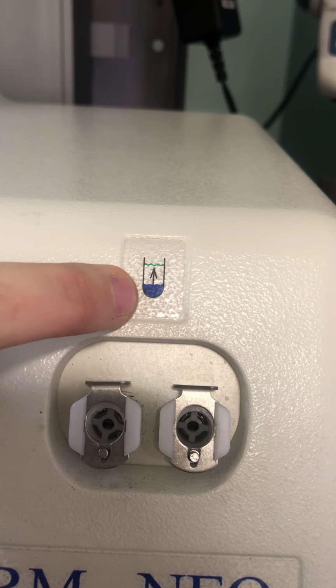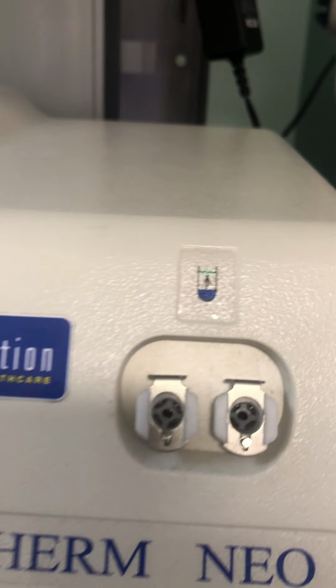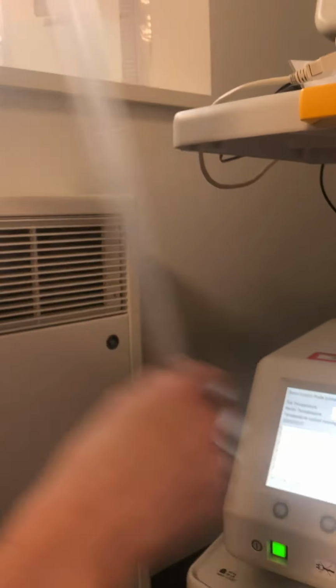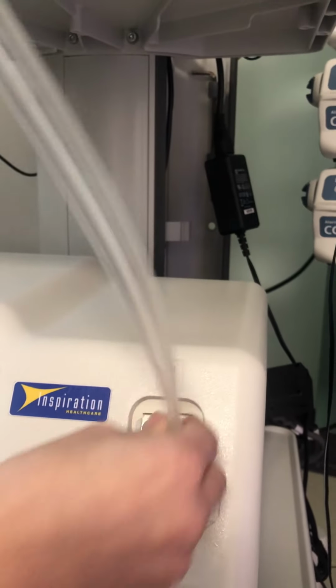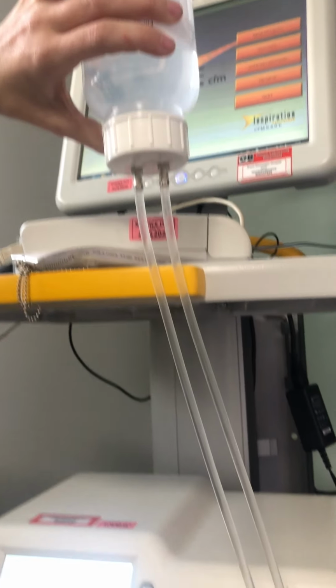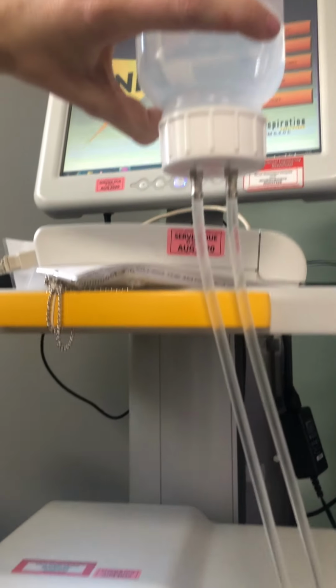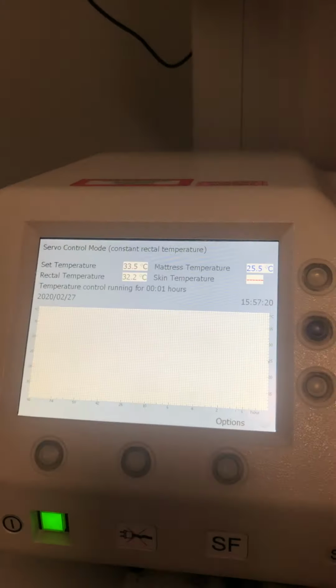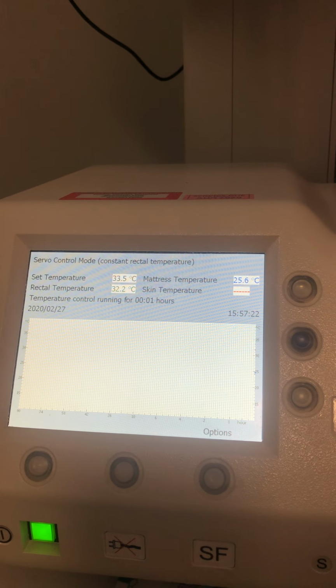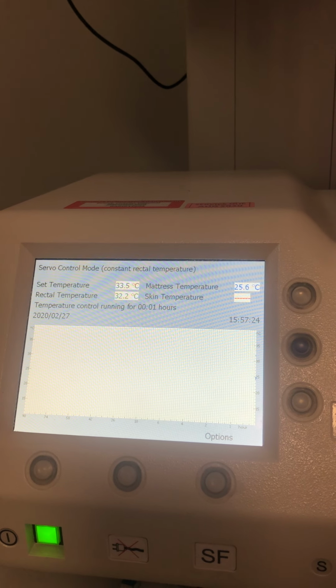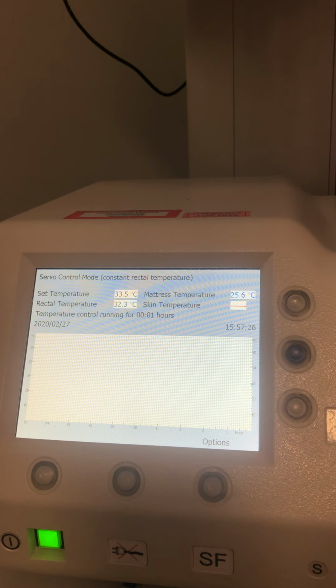What that's basically telling you is the mattress isn't full enough. So you don't need to go out and you don't need to stop it. All you need to do is reconnect your bottle like you had before. Reconnect the bottle and the mattress will automatically continue to cool the baby, but it'll also top up any deficit of water that's been lost when the machine's been put on. Like I said, as long as you top up the mattress beforehand, you shouldn't have a problem with this. It should always fill. This tends to be if you've got a long-term cooler, which we're not going to have.